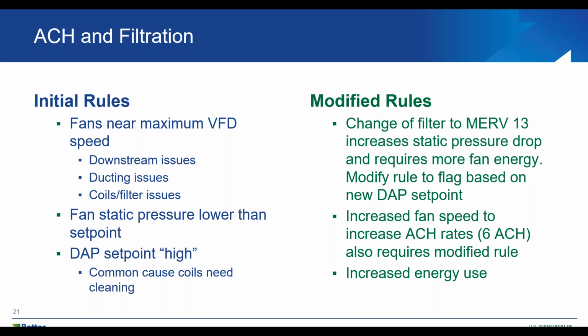However, under the modified rules, you're going to have additional pressure drops, so you need to take that into account in terms of modified rules. And the same thing, if you've increased the air change rate, you need to take that into account by modifying the rules, where you expect to see the fan and the pressures. So they need to accept the new operating conditions that the facilities people and the BAS vendor will implement. And we need to start suppressing flags for alarms if they exist. Next slide, please.